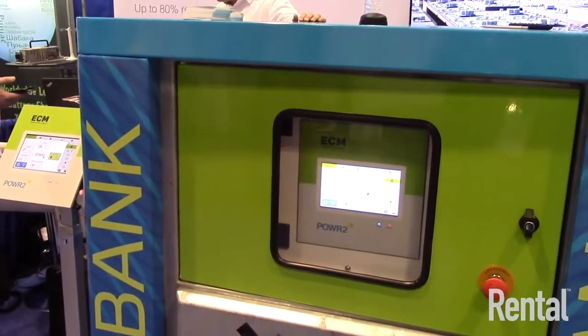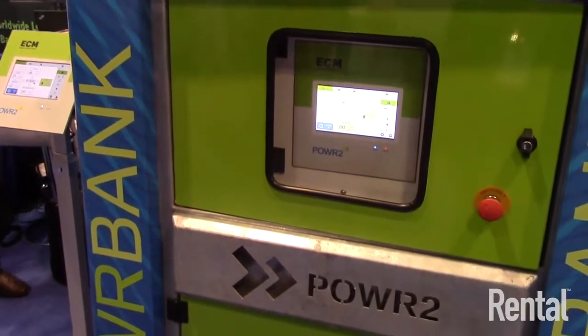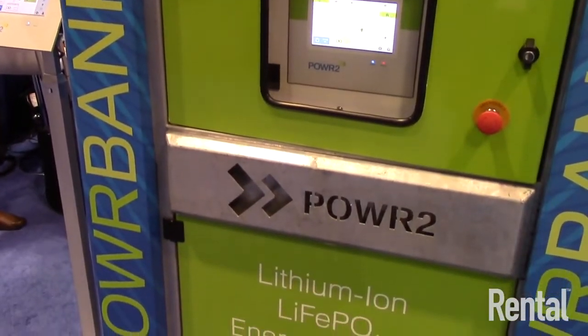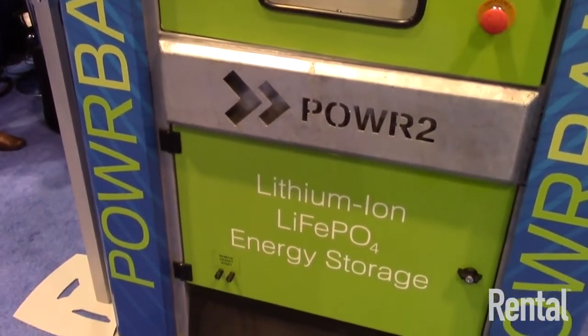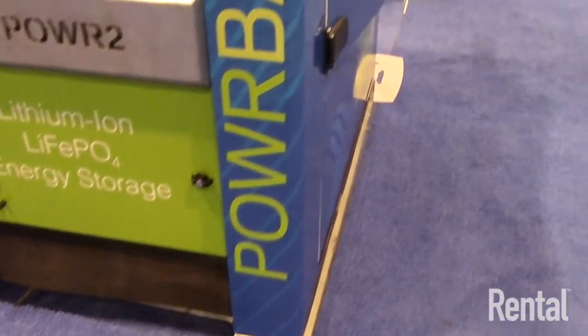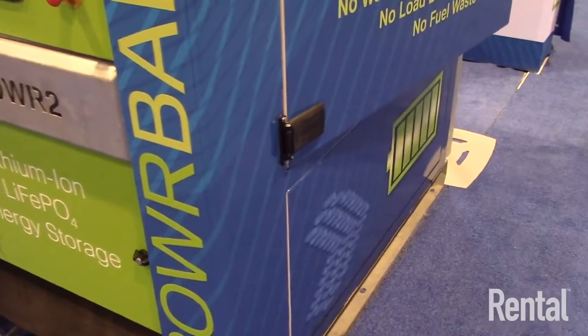Very rugged product. It has a galvanized steel frame, so it's built specifically for the rental market. Other than that, it eliminates service issues with generators such as wet stacking. Tier 4 final generators are very sensitive to wet stacking, and they don't like it, and they will actually shut down or go into regen. So by just making sure they run when they need to, we can eliminate that wet stacking and that service problem.